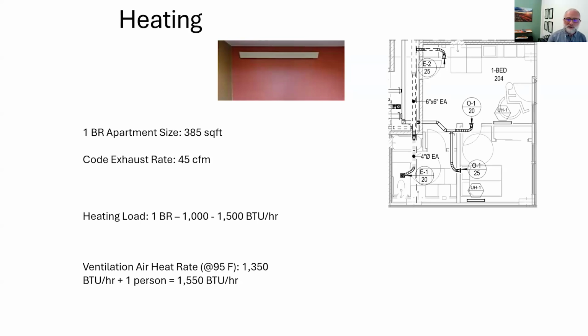However, in order to make sure everyone has a thermostat in the building, we chose to provide electric heat in each apartment. This allows occupants to control their own temperature at the apartment level. So we put in small cove heaters at very modest cost to the project. On the heating side of things for this building, we're able to provide all the necessary heat through the ventilation air, but are giving the tenants small electric heaters so they can control their temperature. So far, so good.